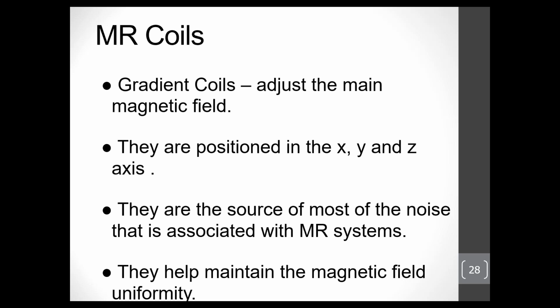One of the things that a lot of people don't know in regards to the MR is the gradient coils. When you walk into an MR, you'll hear that banging and thumping and all that weird noise going on. It's actually from the gradient coils, and they're positioned in X, Y, and Z in relation to the magnets. As they're doing their scans, say they want to primarily focus on the brain, they can goose the main magnet over to where the head is in the scan, and that's where you'll hear the coils and the gradients start making all their racket and noise. This basically helps them focus the scan into a particular area of anatomy.